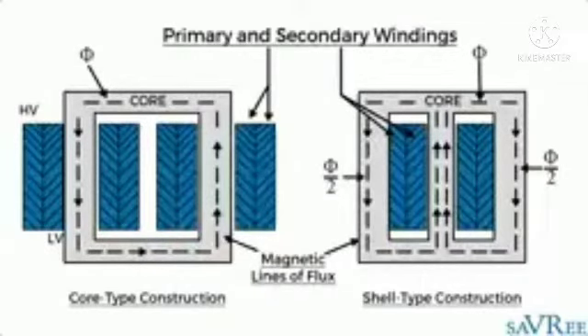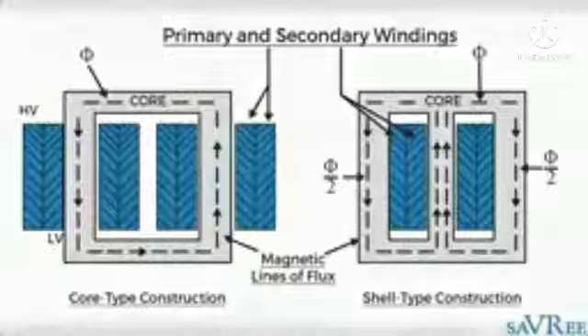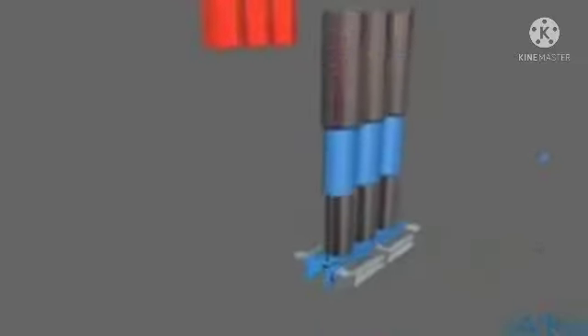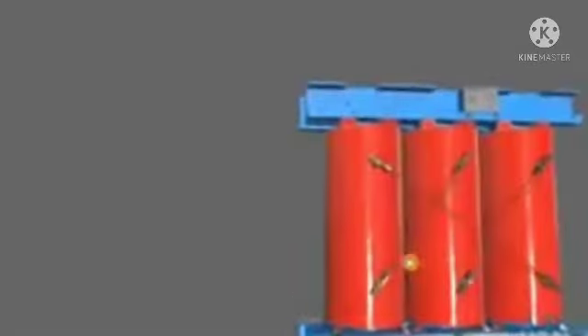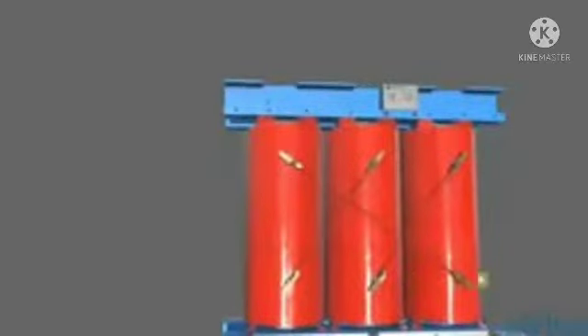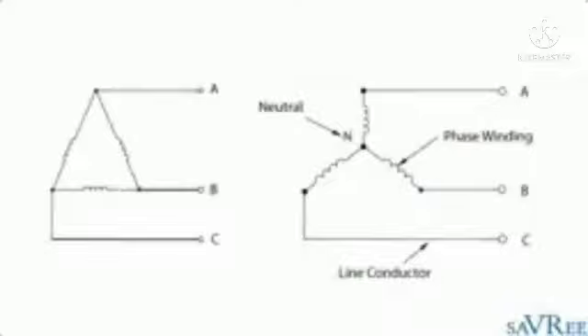So we've got our primary and secondary windings installed, and if we push the play button, we can actually see them coming down onto the core. Here come our clamps, there comes some sort of insulator most likely, and here come some windings and the HV windings that go on the outside. Once that's all assembled, it's going to look a lot like this, and we can see by looking at the back what type of wiring configuration that transformer has.